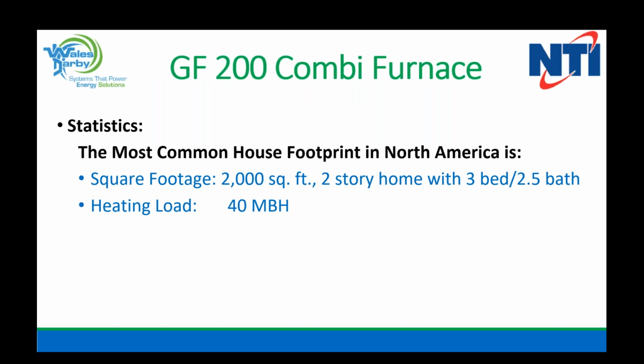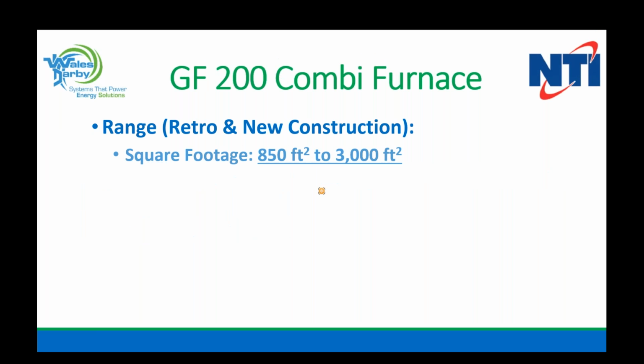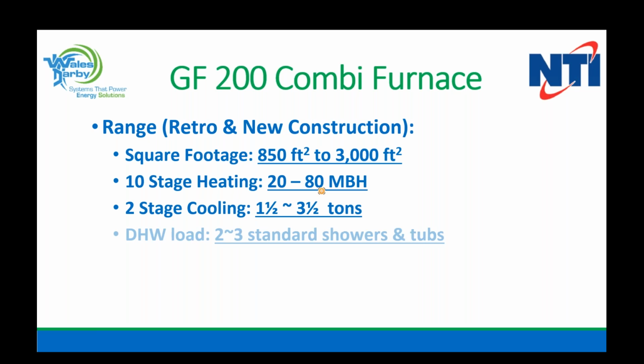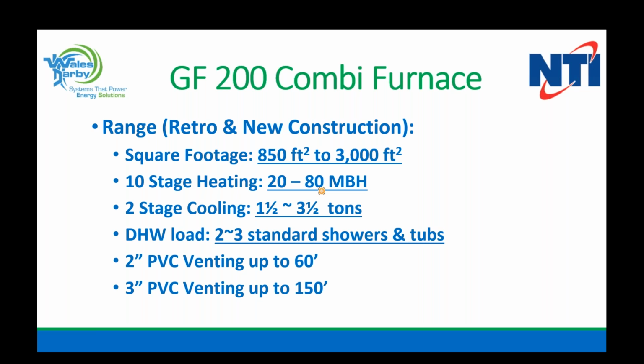So if you look at a typical home, let's say it's a typical 2,000 square foot home, 2-story, 3-bedroom, 2.5 bath, pretty common, right? Ballpark 40,000 BTU, depending on the envelope of the home. 2.5 ton worth of air conditioning, no problem. This is a direct replacement for a system like that. And we'll dive into the details of what the Combi furnace is capable of as we go through the program. So range and ratios here, whether it's a retrofit or a new construction project, you're going to be somewhere in the ballpark of the 850 to 3,000 square foot home.